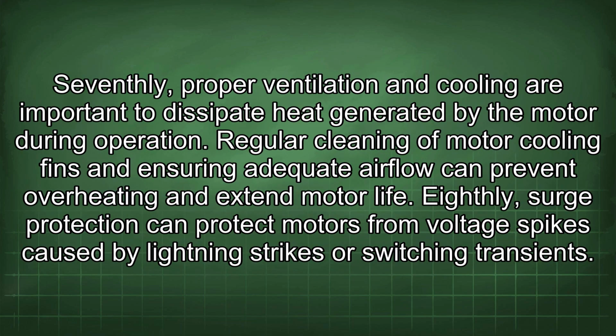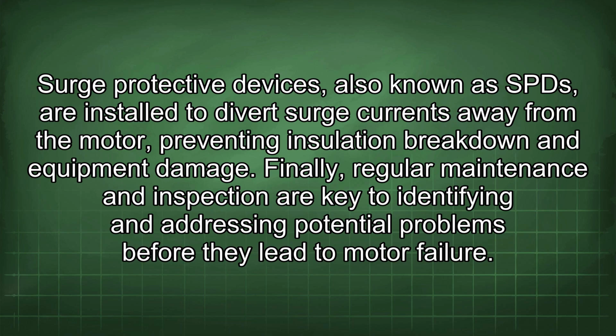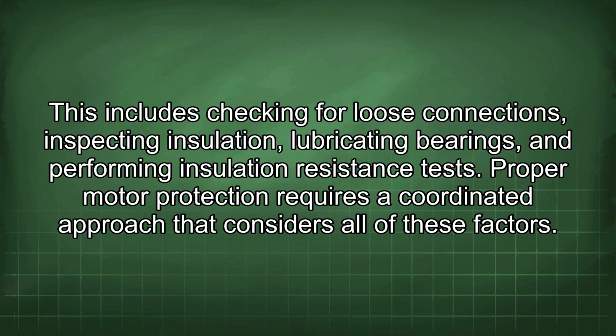Seventhly, proper ventilation and cooling are important to dissipate heat generated by the motor during operation. Regular cleaning of motor cooling fins and ensuring adequate airflow can prevent overheating and extend motor life. Eighthly, surge protection can protect motors from voltage spikes caused by lightning strikes or switching transients. Surge protective devices, also known as SPDs, are installed to divert surge currents away from the motor, preventing insulation breakdown and equipment damage. Finally, regular maintenance and inspection are key to identifying and addressing potential problems before they lead to motor failure. This includes checking for loose connections, inspecting insulation, lubricating bearings, and performing insulation resistance tests.